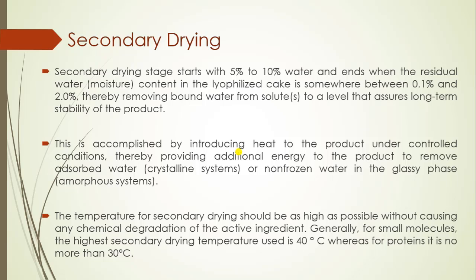In secondary drying, bound water, unfrozen water, or adsorbed water in a solid system is removed, and for this we have to apply high temperature. The temperature for secondary drying is generally around 40 degrees Celsius for small molecules, and for larger molecules like proteins it is around 30 degrees Celsius.